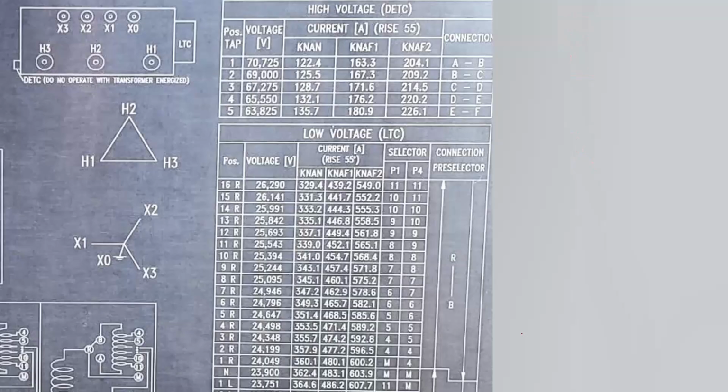So I got one more right here, and this is what we're going to look at: what's our primary voltage? Well, we have a de-energized tap changer on the primary, and depending on how you test it, what are you connected to? You have to identify this. So we're just going to use the nominal tap, the middle one right here, and we're just going to say that it's tap 3, and then we're also going to use the neutral tap on the load tap changer, so you've got plenty of voltages there.